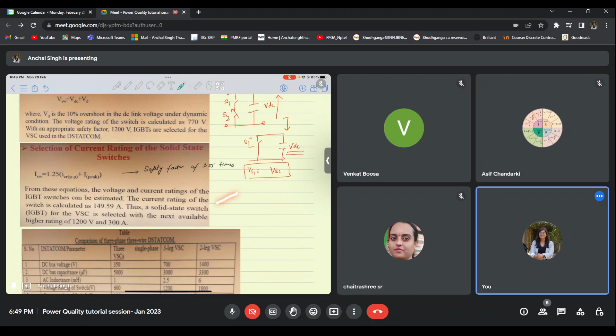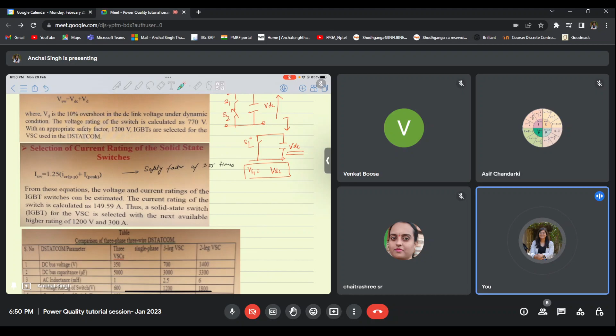Similarly, the current. So when we know that the current waveform is something like this, and this is the steady state value of the switch current that we obtain. So the ripple current, the peak value of current, the steady state peak value of the current, plus the maximum ripple that I'm expecting, with a safety factor of 1.25 times. 25% extra we are taking. Why? Because it's just a factor of safety thing. So you could take it 1.2 times, but normally in industry we take it 1.25 times.